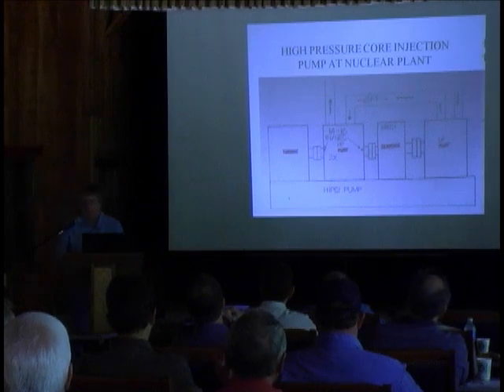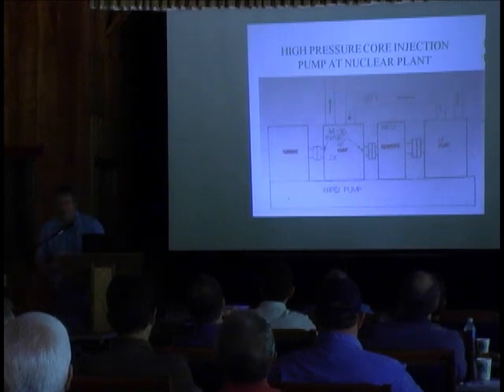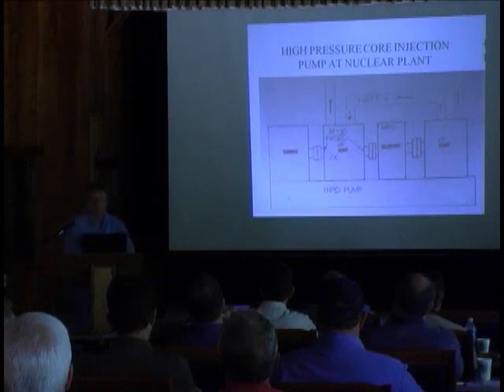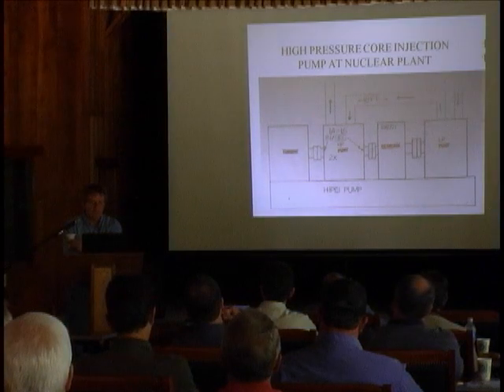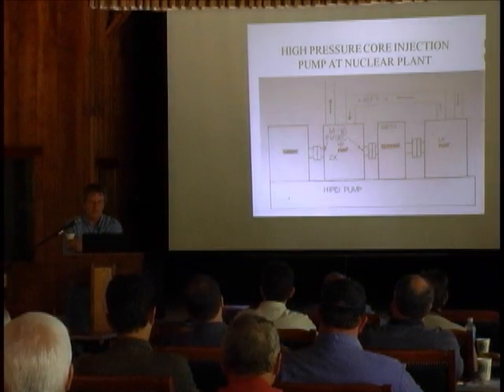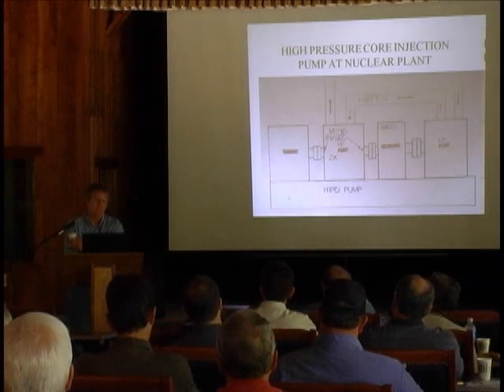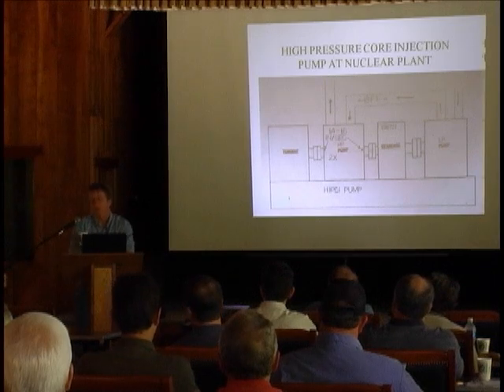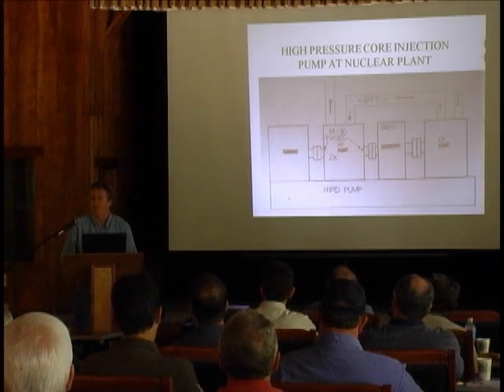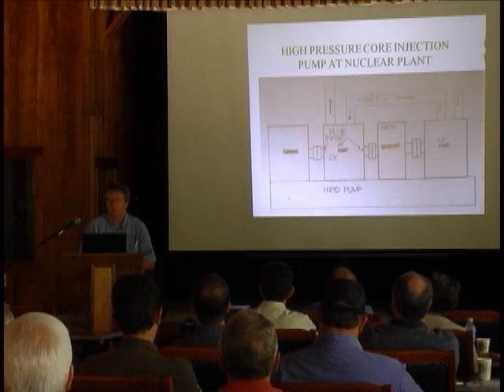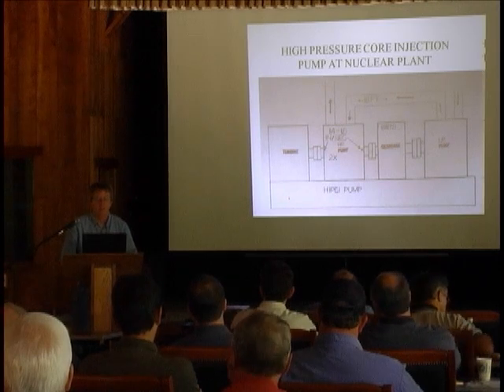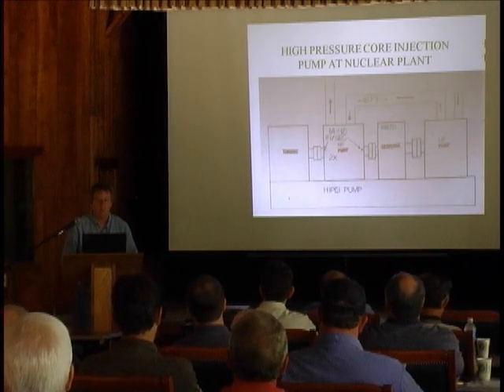Most of you probably haven't dealt with nuclear plants, and you're lucky in that aspect. But basically, they have what are called ASME Section 11 requirements for vibration analysis. And in the old days, it was really pretty simple. You took baseline readings, and then if the readings doubled in mils, then you had to do something. They didn't do velocity, no spectrum or anything. So this pump had been in operation, and its mil level hadn't doubled, so nobody worried too much about it.